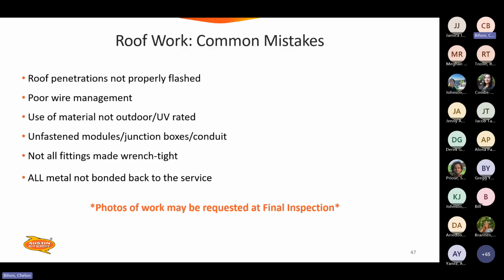Roof work, common mistakes. Roof penetration is not properly flashed. Poor wire management. Use of material not outdoor rated, UV rated. Unfastened modules, junction boxes, conduit. Not all fittings made wrench tight. All metal not bonded back to the service.